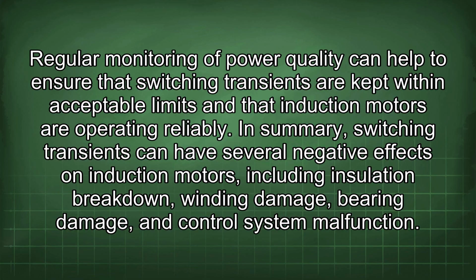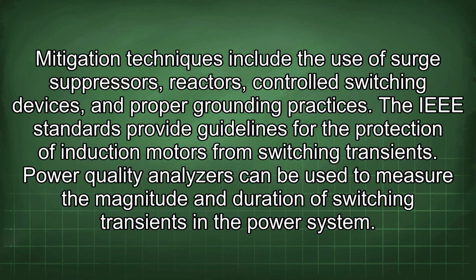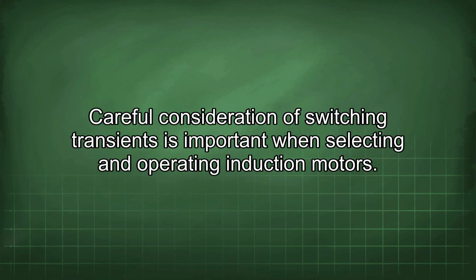In summary, switching transients can have several negative effects on induction motors, including insulation breakdown, winding damage, bearing damage, and control system malfunction. Mitigation techniques include the use of surge suppressors, reactors, controlled switching devices, and proper grounding practices. The IEEE standards provide guidelines for the protection of induction motors from switching transients. Power quality analyzers can be used to measure the magnitude and duration of switching transients in the power system. Careful consideration of switching transients is important when selecting and operating induction motors.